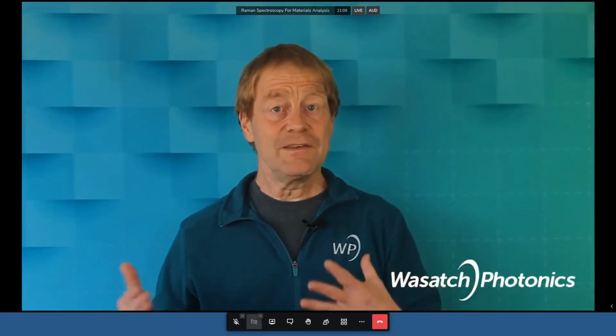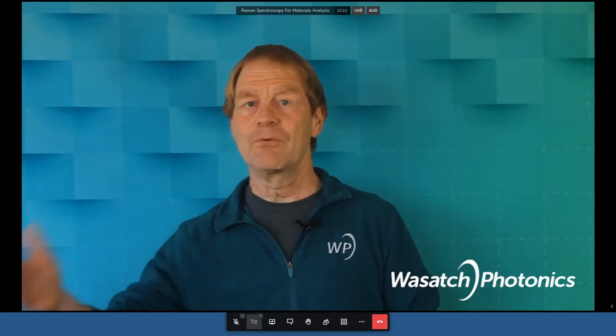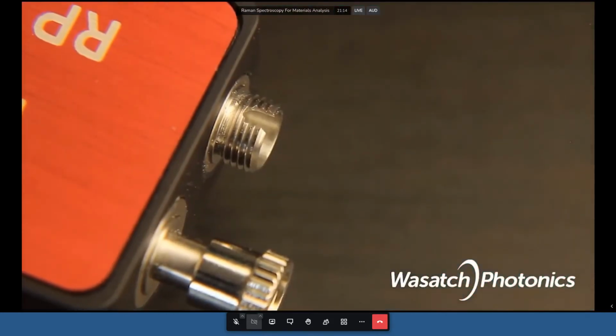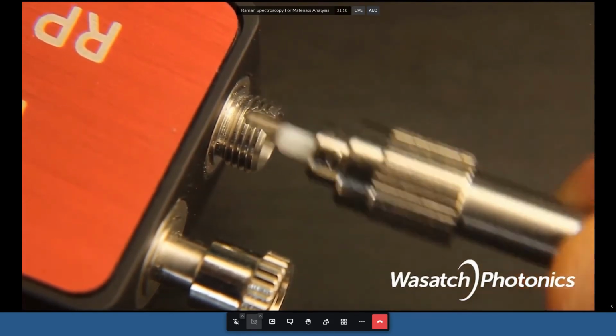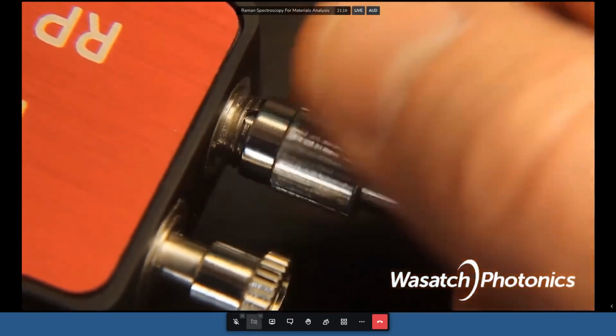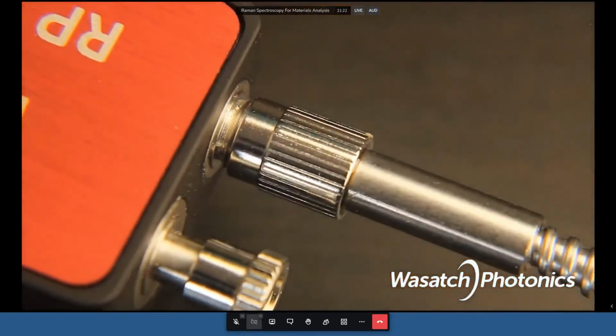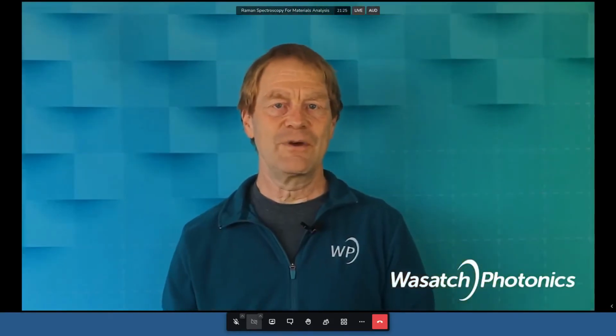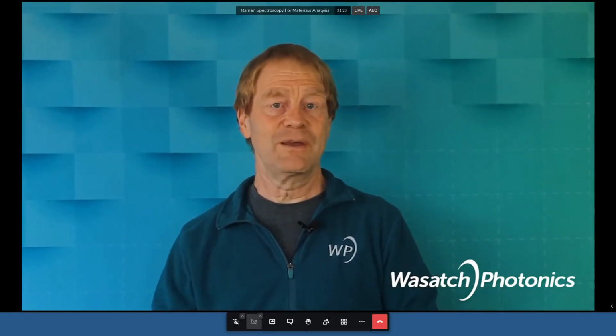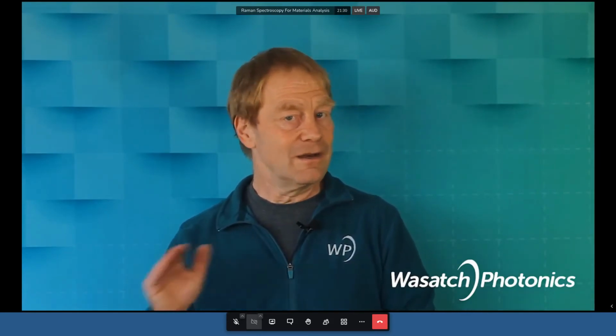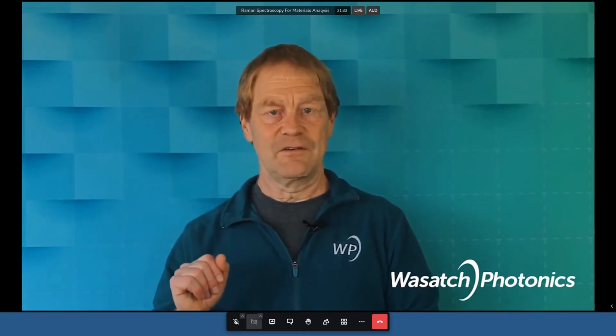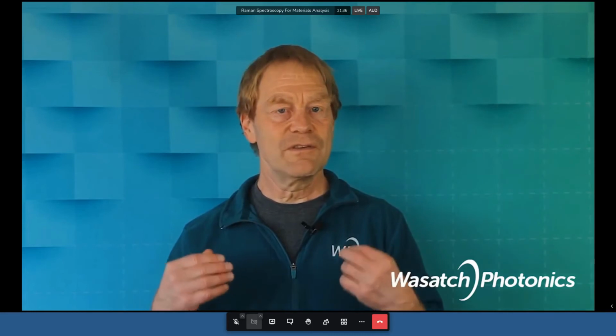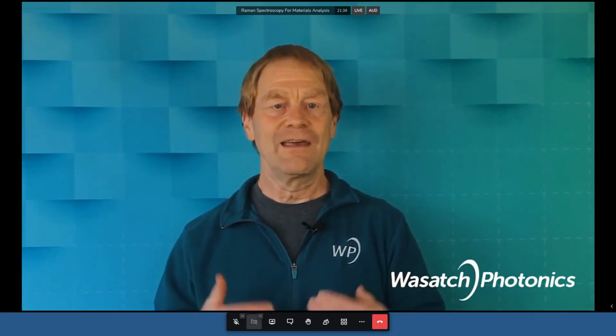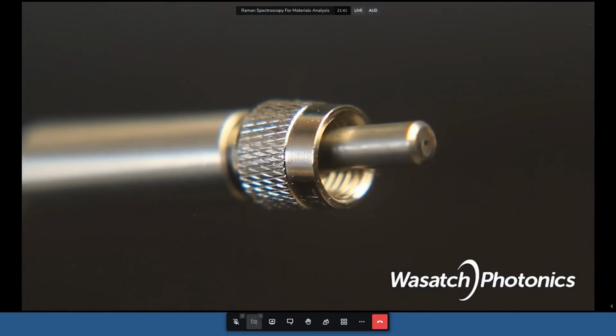The same FC-PC connection you will also find at the Raman probe end. Again, there is a notch on the receptacle and a stub on the FC fiber. As with the laser, orient the fiber the right way, insert and finger tighten. For a fully integrated WASATCH Raman system, the probe is already built into the spectrometer and no fiber connection is needed at all. Next, we connect the spectrometer to the probe. This is done with a second optical fiber, which has the so-called SMA connector. The SMA fiber has a metal tip and, unlike the FC fiber, does not have a stub, so the orientation does not matter.